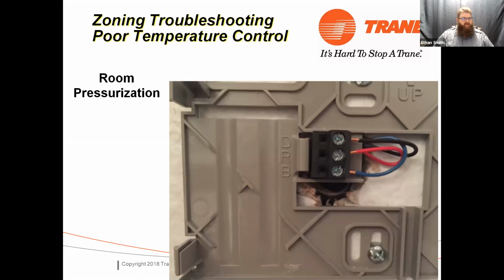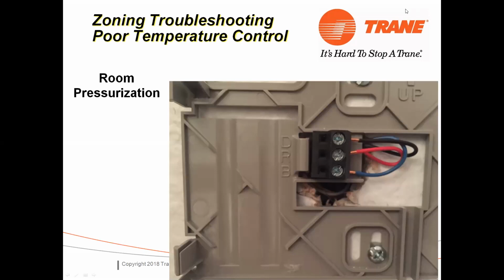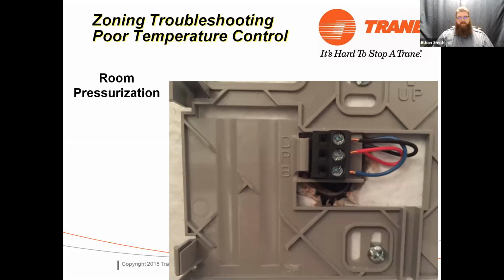So we're looking at the sub base of this zone sensor. Why on earth would this zone sensor give me inaccurate temperature readings? Because you're using the furnace transformer wire. Nope, this is a communicating zone sensor. It can pull power from the zone panel.